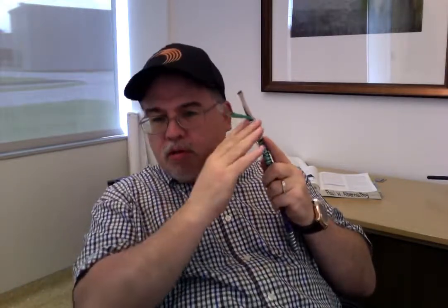Again, just so you know, also with the healthcare facility one, you simply take this 10 gauge aluminum, bend it back, cut it off, so that it doesn't protrude past the outside perimeter of the actual armor. That way the fitting will fit on properly, or the connector, and then you're done. You don't need to do anything else with it. Again, that's all that you need to do for that.